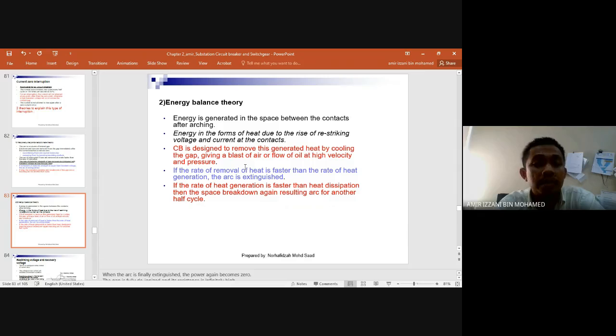Okay, the second one is energy balance theory. Energy is generated in the space between the contacts after arcing. Energy in the form of heat due to rise of re-striking voltage and current at the contact. The CB is designed to remove this generated heat, which is a form of energy, by cooling the gap, either by blowing an air blast, a high speed air, or oil at high velocity and pressure.